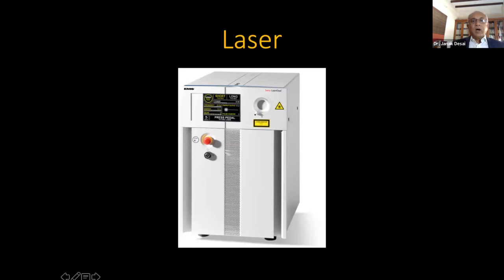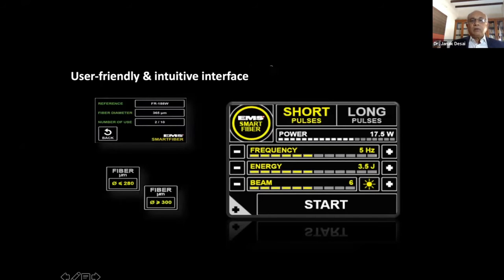I told you why, because we need to put it through flexible routes also, in Flexi URS and in the miniaturized PCNL. So we have this very sleek toy which produces excellent short pulses as well as long pulses. We can play with that depending on what you want. The short one is for quicker, faster delivery of energy, and the long one is to keep the stone not flying away, more for dusting. So you can adjust that, the frequency and energy.